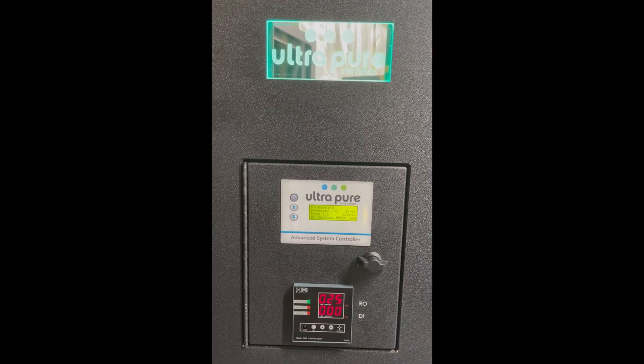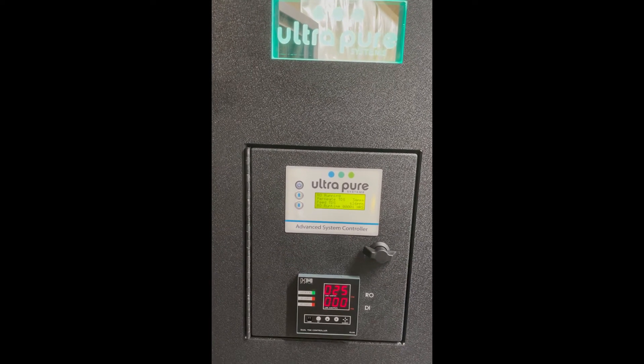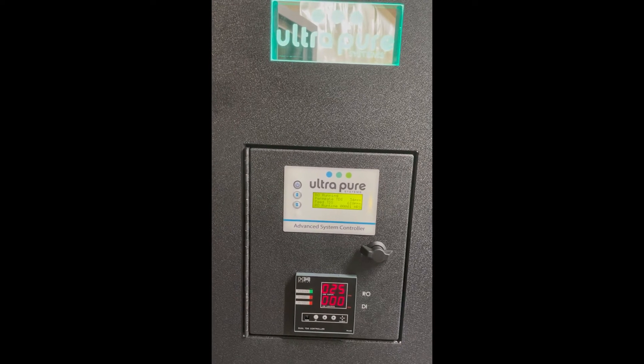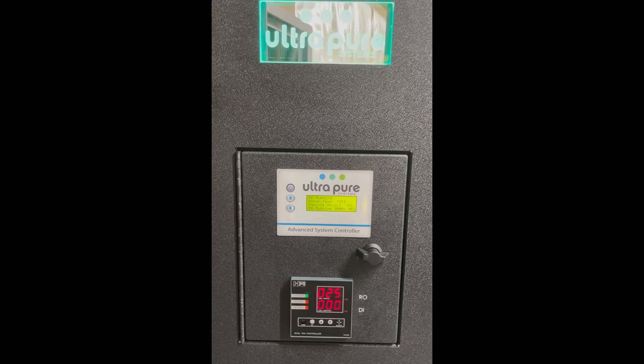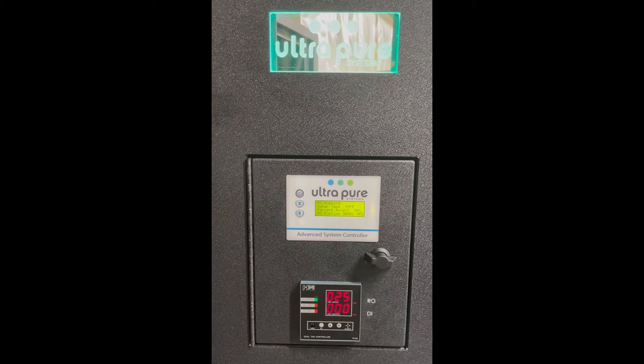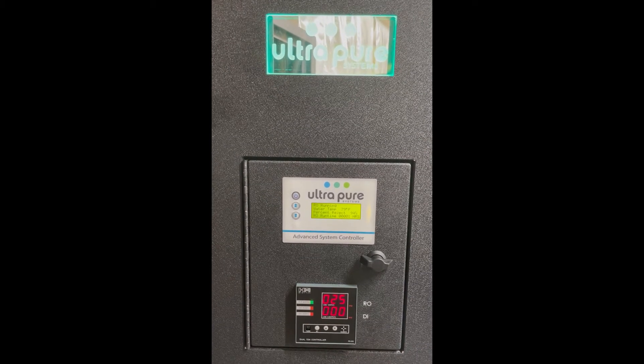This is an 800 gallon per day system that's currently being wet tested in the shop. It's running very well — we're at about 25 parts per million on the reverse osmosis membrane. We do not test DI during wet testing to keep the resin as moist as we can and not send it dry, so that's reading zero currently.